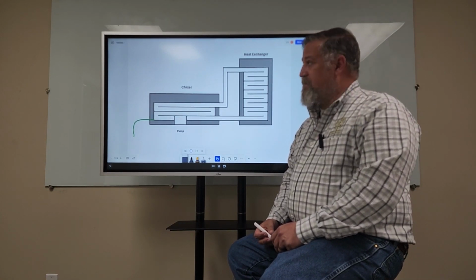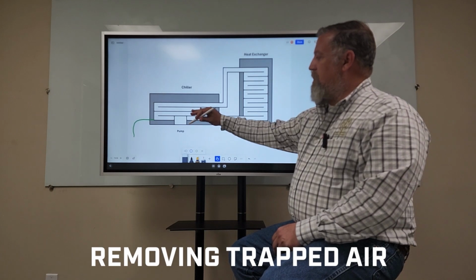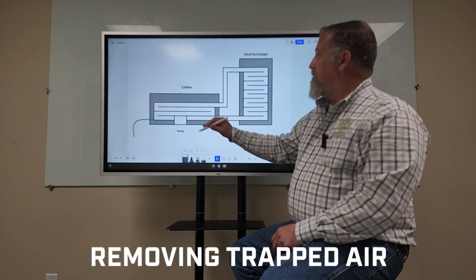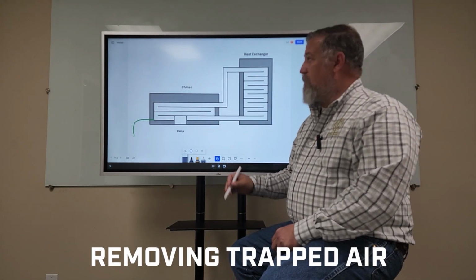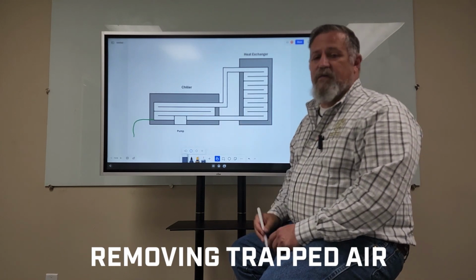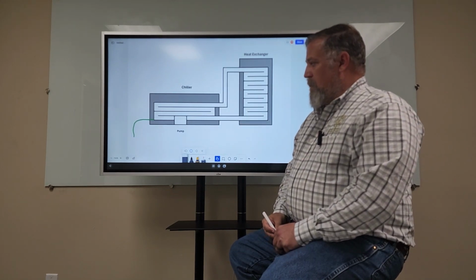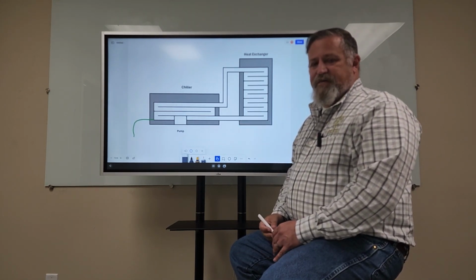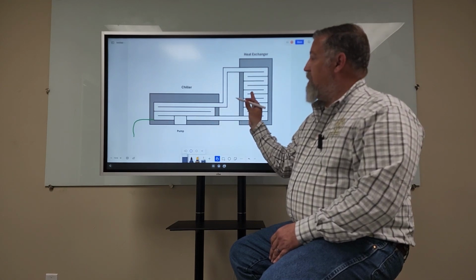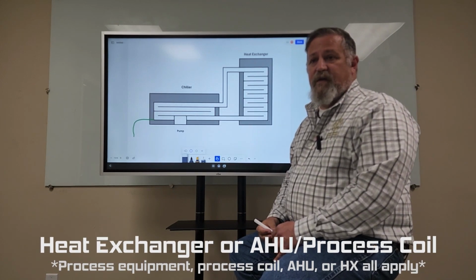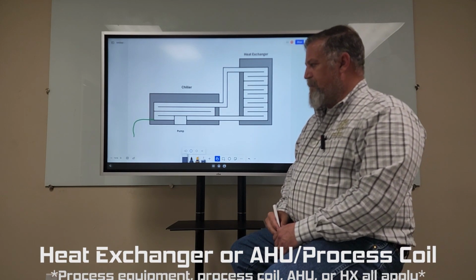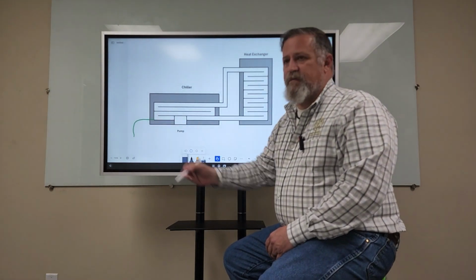And today, our service bulletin is going to be over the proper fill method for filling a chiller with a heat exchanger and removing trapped air pockets that are in the system. The most important part of the process of setting up a chiller and a heat exchanger is going to be the fill process. And so our first step is we're going to attach our filler hose, okay?